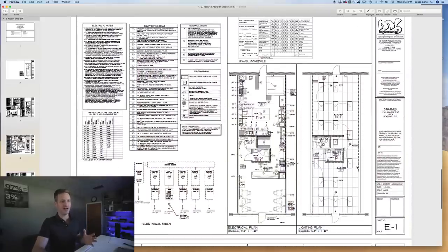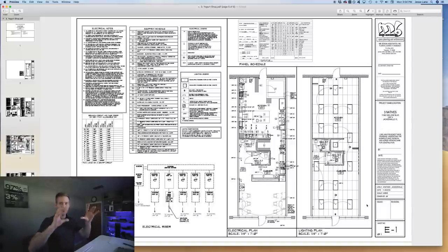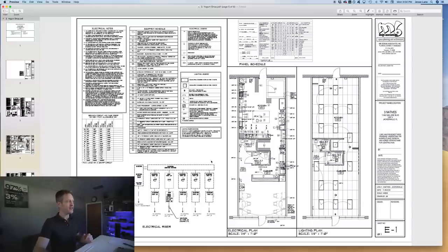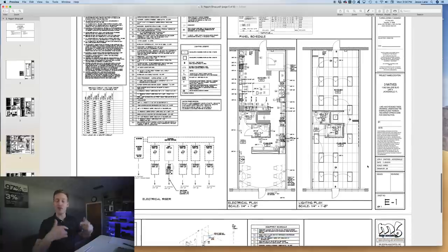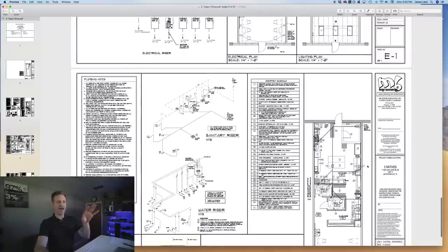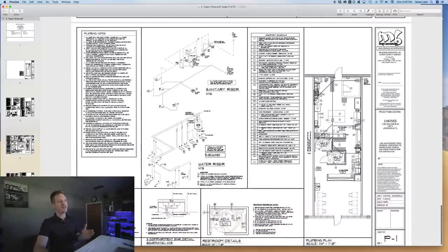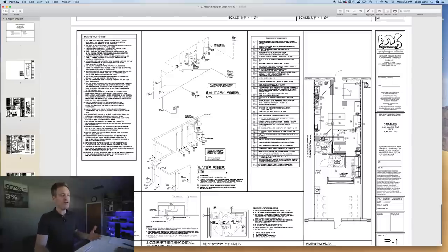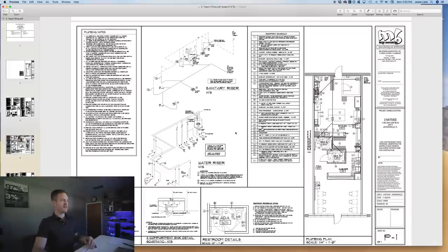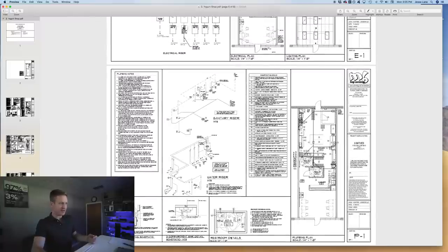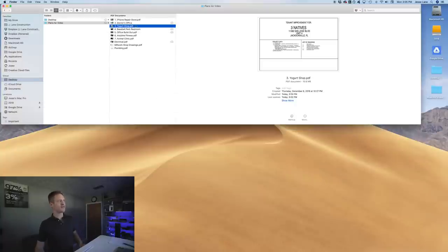The electrical plan, E1, shows the electrical riser, phasing, where each light fixture and outlet goes, how each wire ties into each circuit, and how it home-runs back to the panel. We were adding a new panel on this job. The plumbing plan, P1, shows the sanitary riser and water riser — the water riser covers supply from the water heater to the building, and the sanitary riser shows where waste exits through a three-inch line out to the sewer.